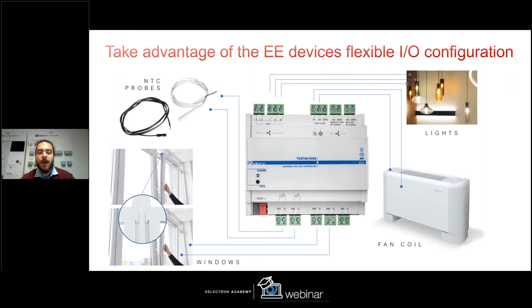So we can use a room module like our 1925 thermostat as control panel, or enable the regulation algorithm directly inside the 1925 thermostat and use the TC57 as a passive module. So in this particular case, we enable the thermostat function in the 1925 thermostat that will send the command over the KNX bus to the fan coil actuator, and the fan coil actuator simply will act on the command received from the thermostat. I remind you that our 1925 series can control and manage different kinds of HVAC system.